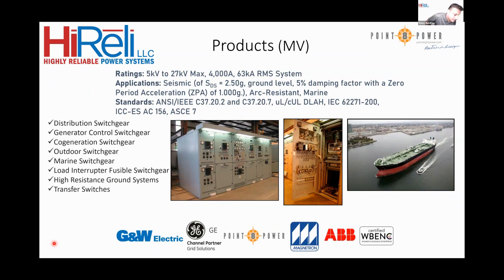and the requirements. So as Alex mentioned earlier, there's a project that we just embarked on that requires 15 kV outdoor non-walk-in stainless steel switchgear. The specifications for the paint system have to meet the C57.12.29 standards. What this means is that the facility has to be able to meet the standards in the paint system, and this was required by a naval facility out on the northeast coast.